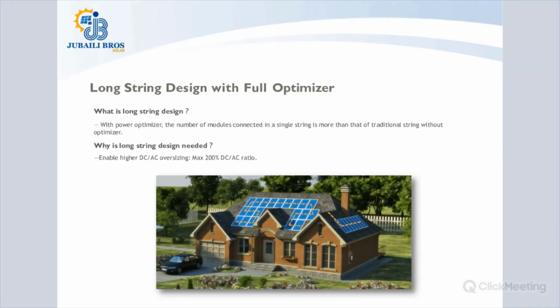So again, moving one step forward. The long string design, as I tried to explain earlier: we all know how traditional designs are made, where there is a calculation of the maximum number of PV modules that can be in a string. With the long string design, the optimizers allow us to do strings that are longer than the traditional type. And this enables us to actually ramp up the DC to AC ratio.